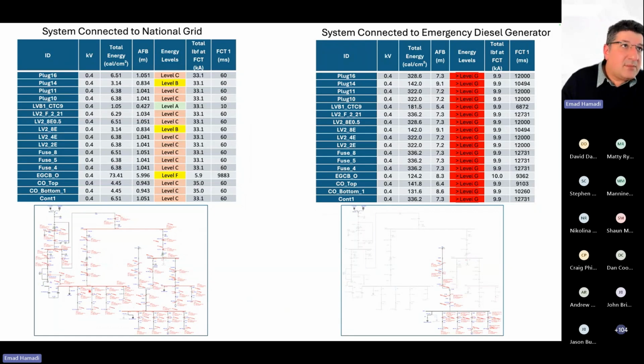So this is the system connected to the DNO, the national grid, and this is when the system is connected to the emergency diesel generator. As you can see, these are the same points, and when connected to the diesel generator the energy level is very high. The fault current is lower compared to when it's connected to the national grid, but because of the clearing time, the tripping time, the energy level is very high. This situation is particularly concerning because emergency diesel generators are typically in service during a power outage or critical situation, which is also when personnel are more likely to be investigating the issue and working close to the panels. Therefore, the risk of exposure to high incident energy is greater.